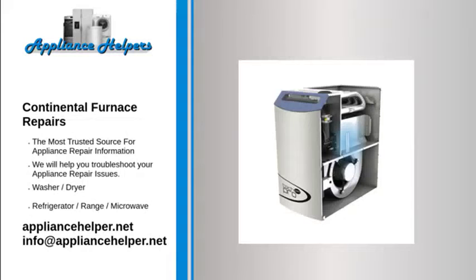Is the power on to the furnace? If the fan is not running, check the breaker, fuse, and/or the switch for the furnace. If the breaker was tripped, leave it off and check the furnace wiring for loose connections. Also, you should look for burn spots on the control board and replace the board if spots are found. After any necessary repairs, the breaker can be reset.